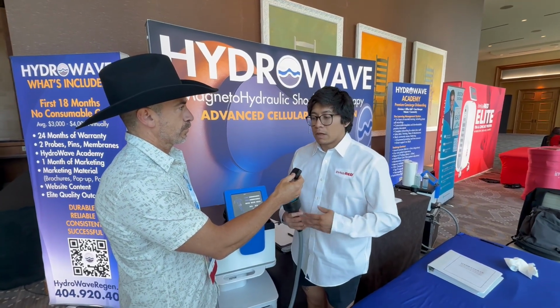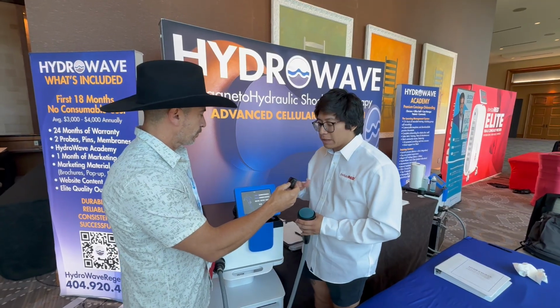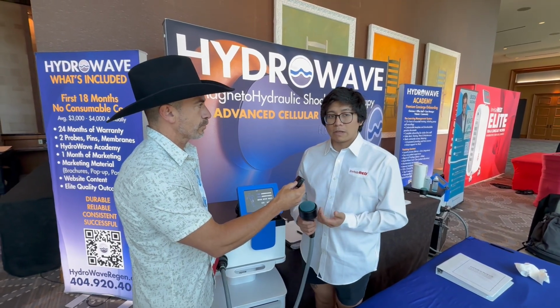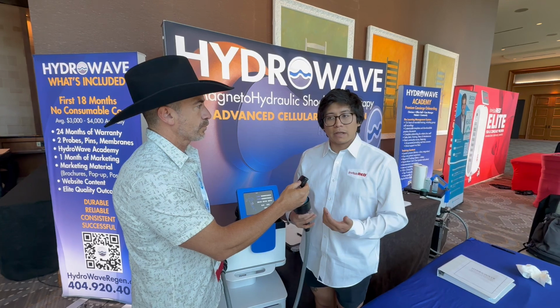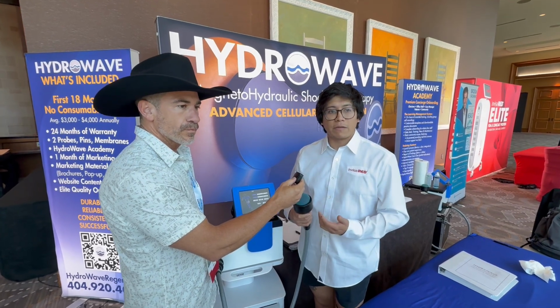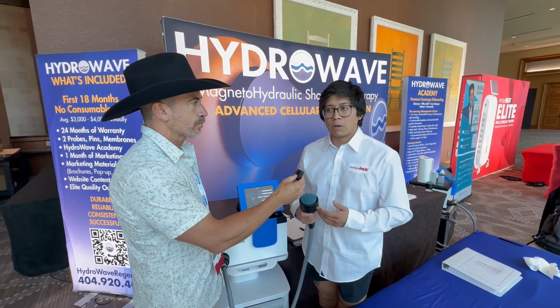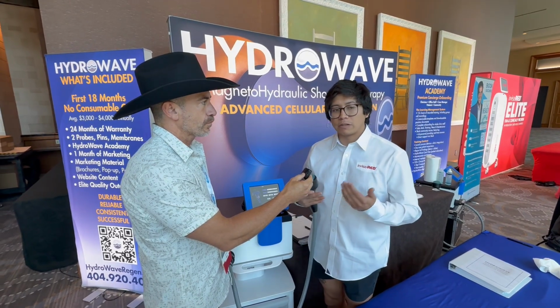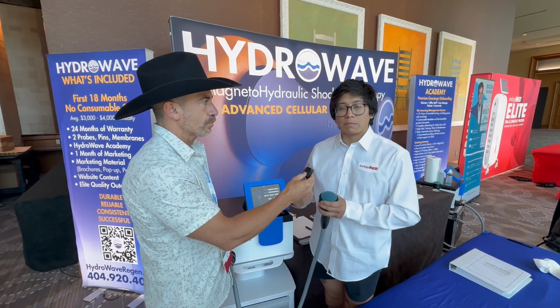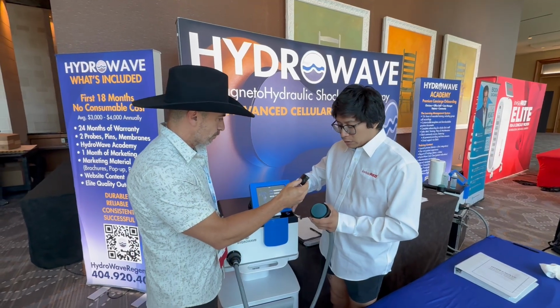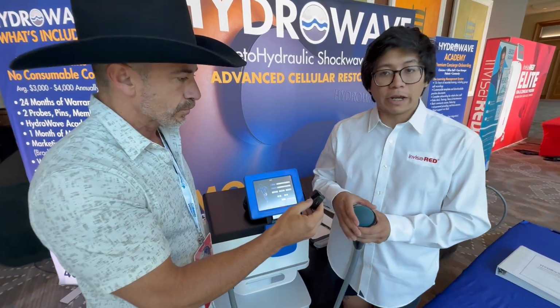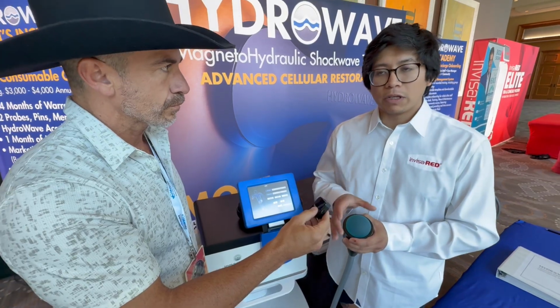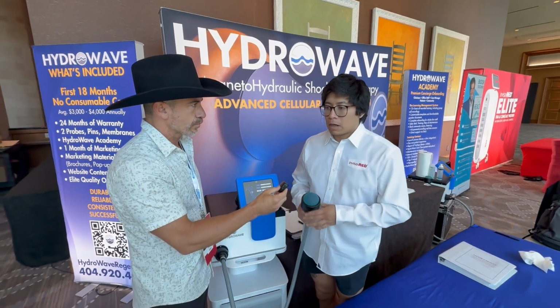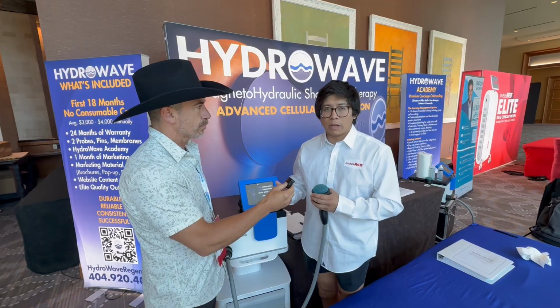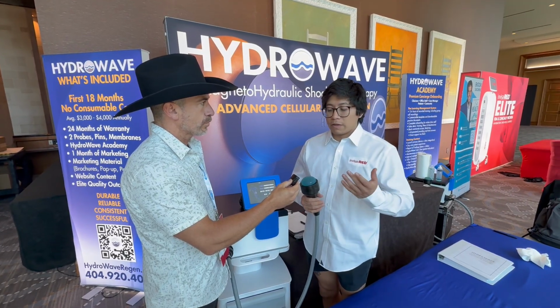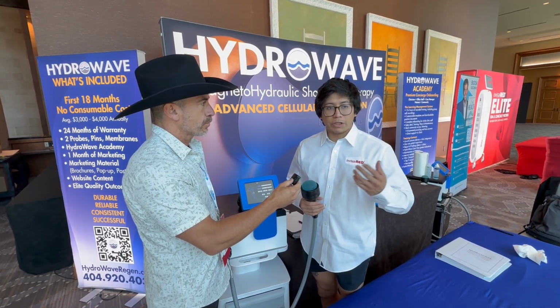Now, what makes Hydrowave different from anything else is that you can do a broad focus shockwave, so you can scan the area to find where the inflammation is for your patient, and then based off their tolerance level, start treating that area. Once that area gets treated over time, you can get it even more focused by increasing the pressure of the head, so you can actually pinpoint the specific area where the injury is happening. So you can put all the energy of the machine, let's say it is 0.01 millijoules of energy, that is going to help the body regenerate.